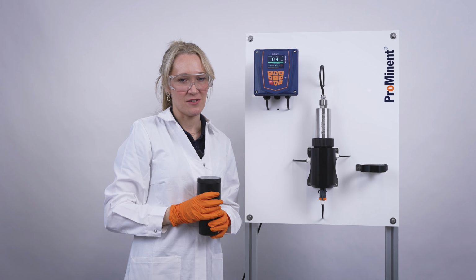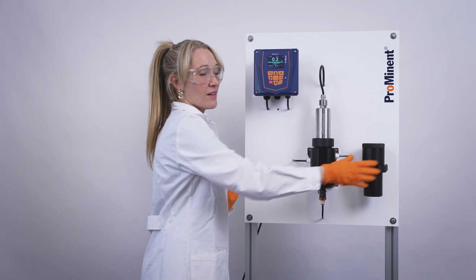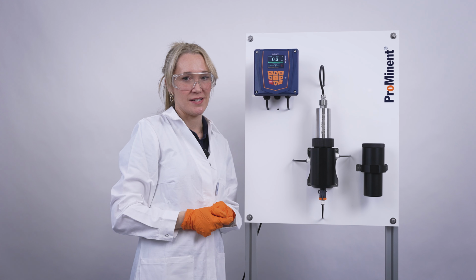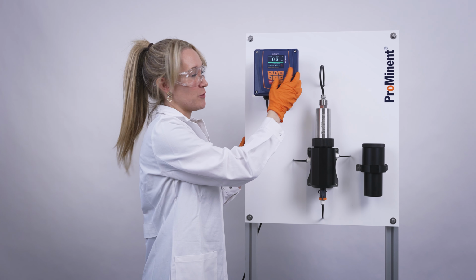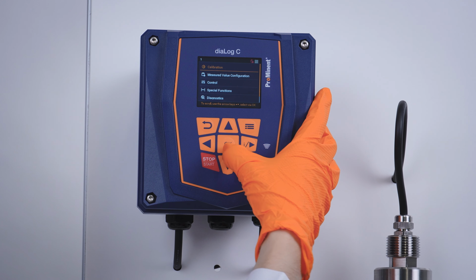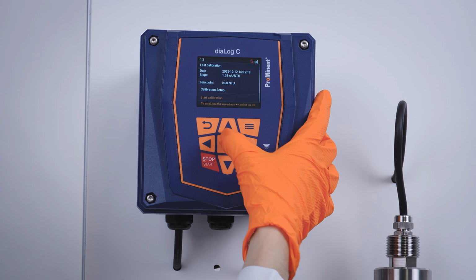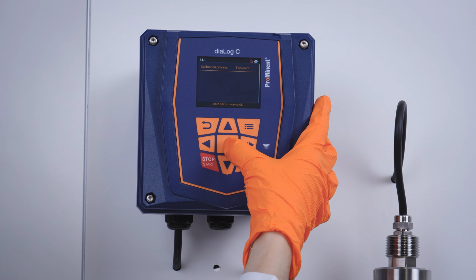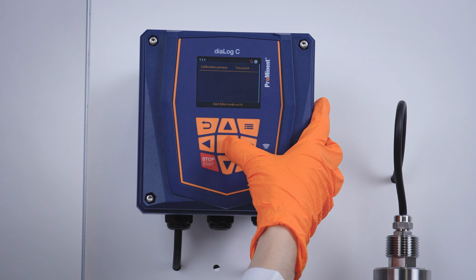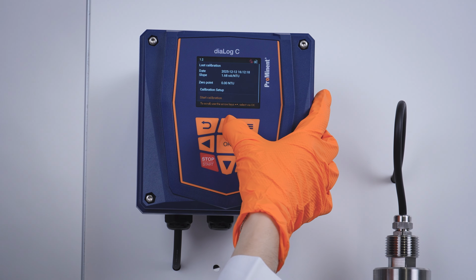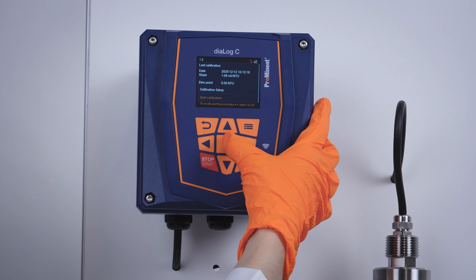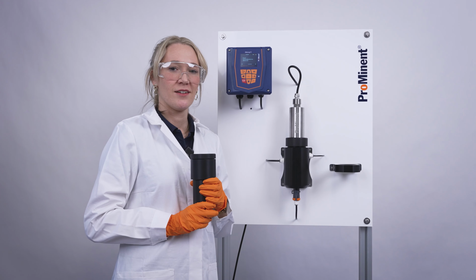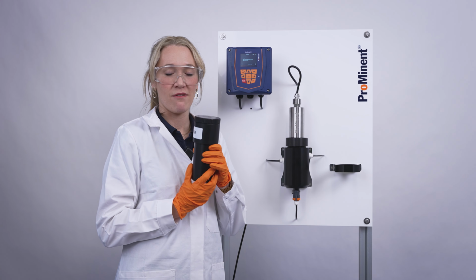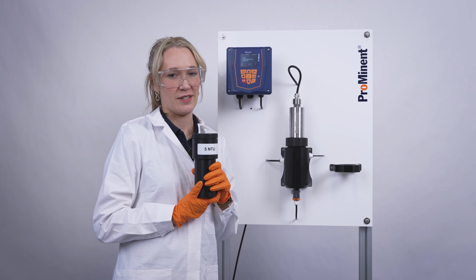After filling the calibration vessel, we start the calibration on the controller side. Therefore, we go to the menu, Calibration, Calibration Setup, and then we choose the 2-point calibration. After doing so, we can start the calibration. Today, for demonstration, we use 5 and 10 NTU for calibration.